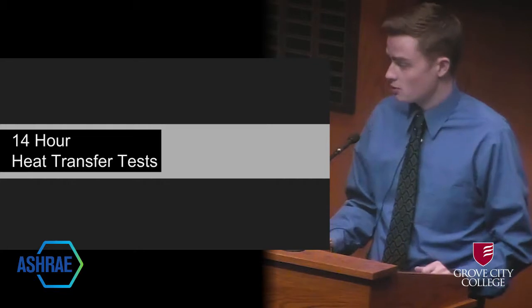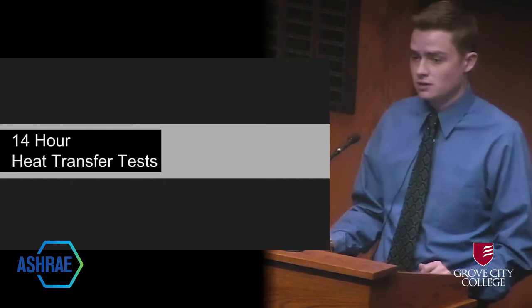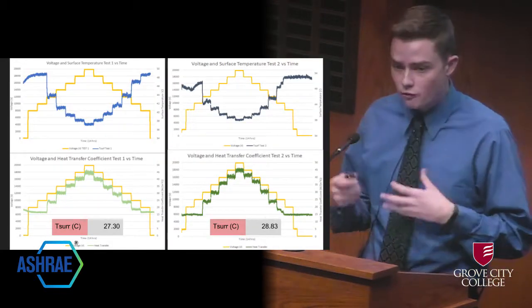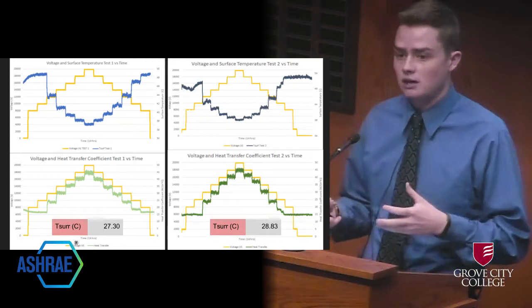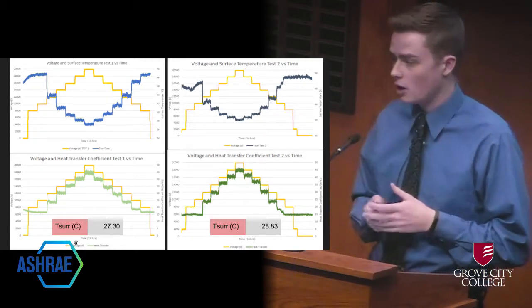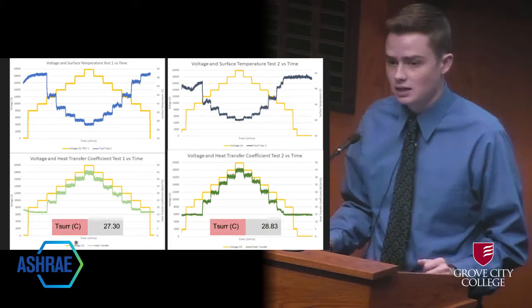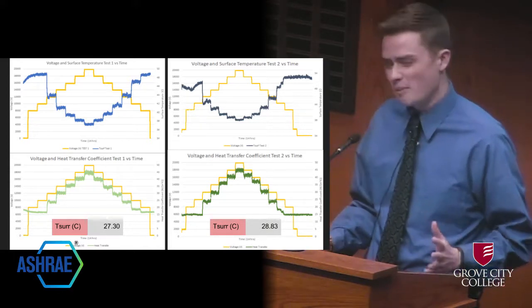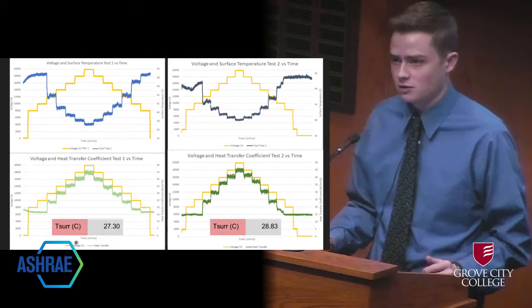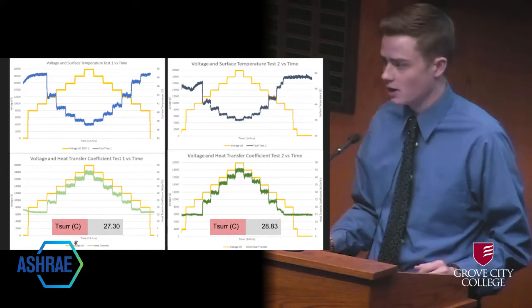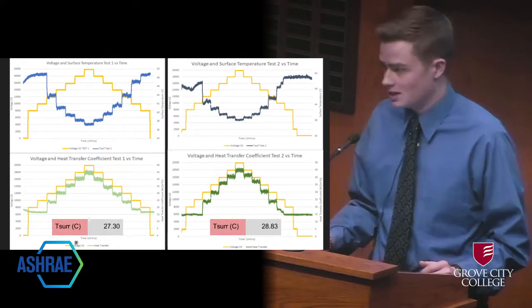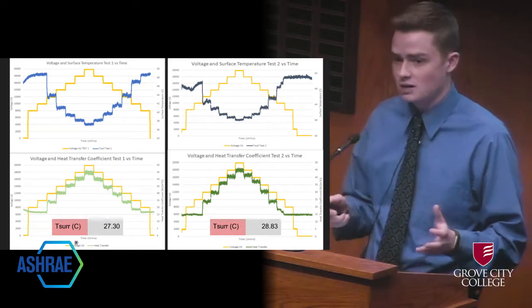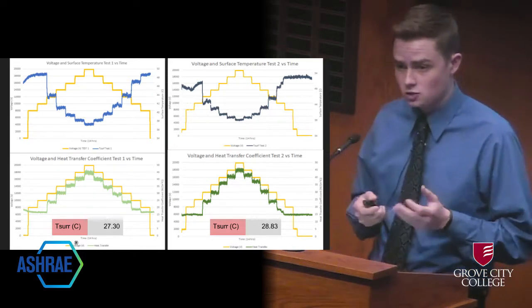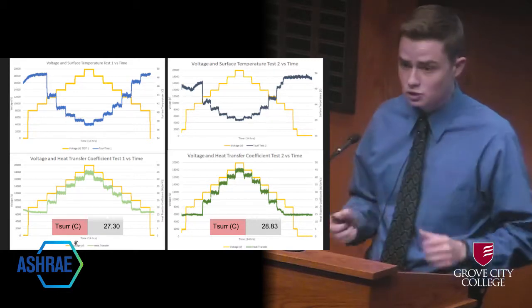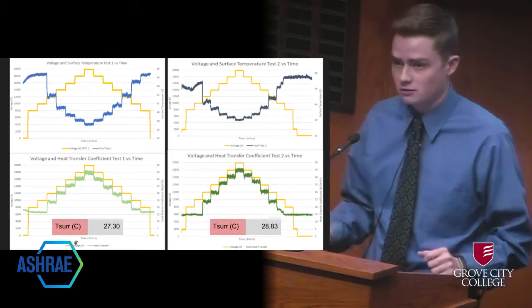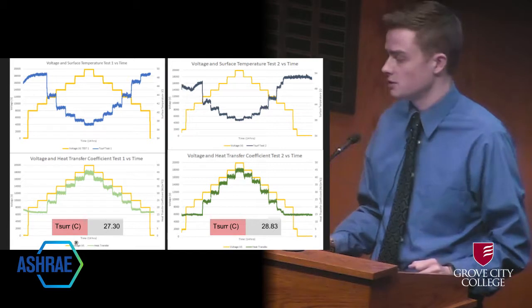Another test we ran was two 14-hour heat transfer tests. Here are four different graphs, done four days apart. At the bottom you can see the surrounding temperature, which was about 1.5 degrees Celsius off from each other overnight. This was a 14-hour test where we varied the voltage starting at 0, to get a base reading, all the way up to 20 kilovolts in increments of 2,000 volts.